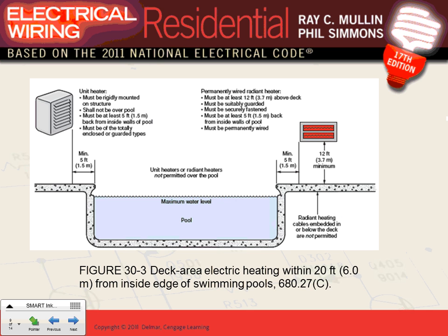Okay, so that's what we're covering. Then the code goes into details on how to put heaters around a swimming pool, indoor and outdoor. Suppose this is an indoor swimming pool and you need to put in a radiant heater like this. Here's the requirement for a radiant heater like this one. You can't put it closer than 12 feet because of the hazard of electrocution. You also can't put it closer than 5 feet from the inside of the pool. Can you guys see that?